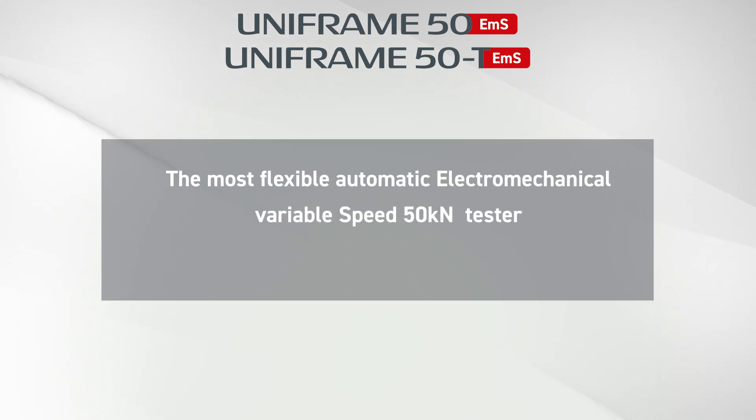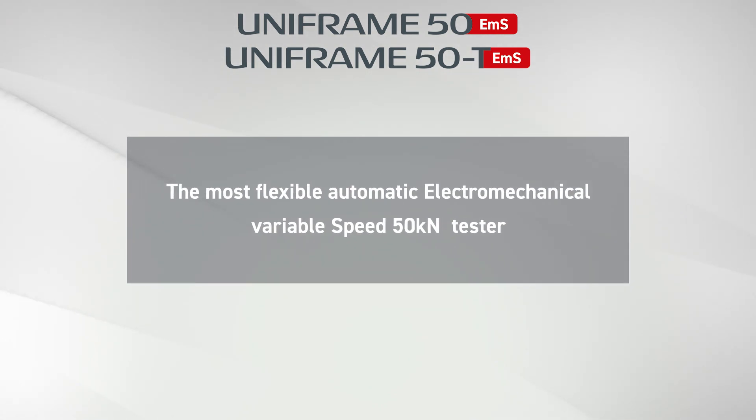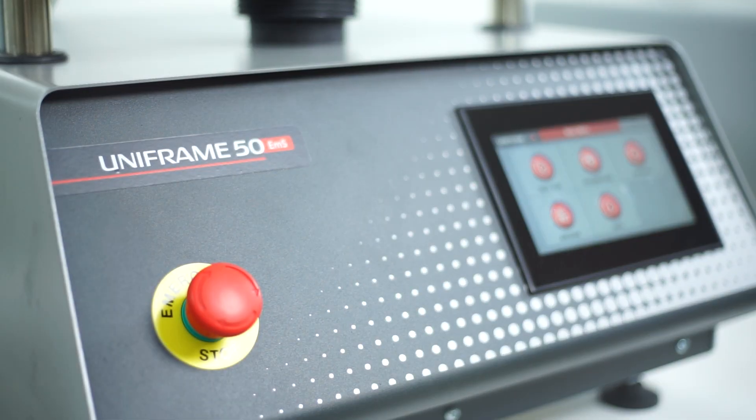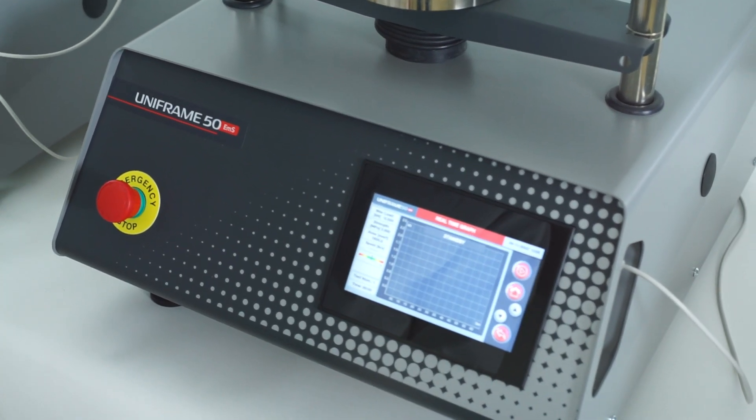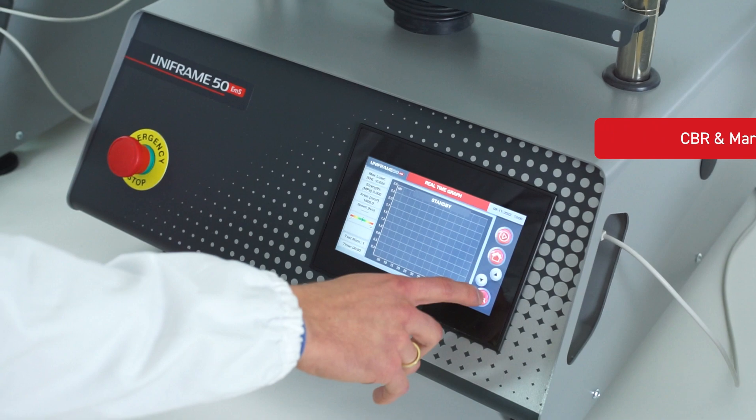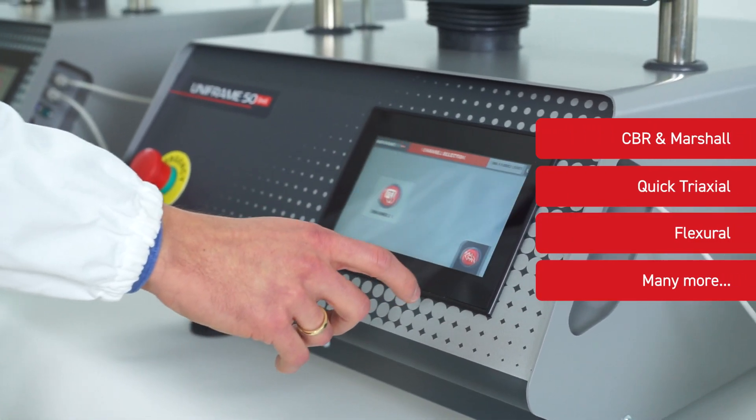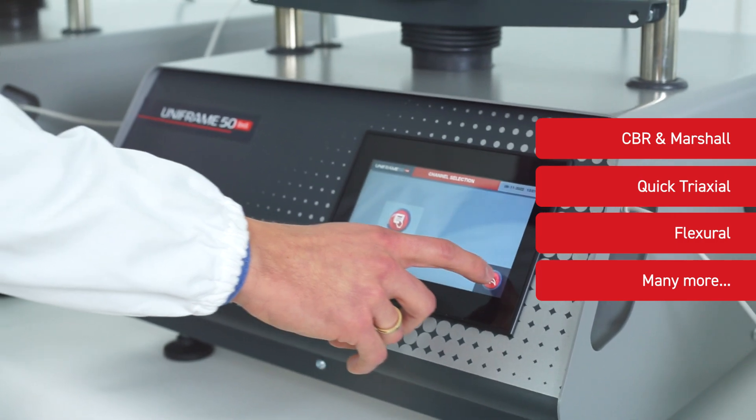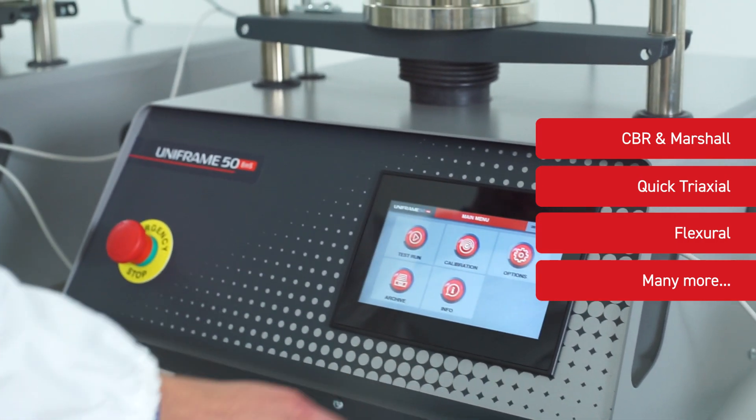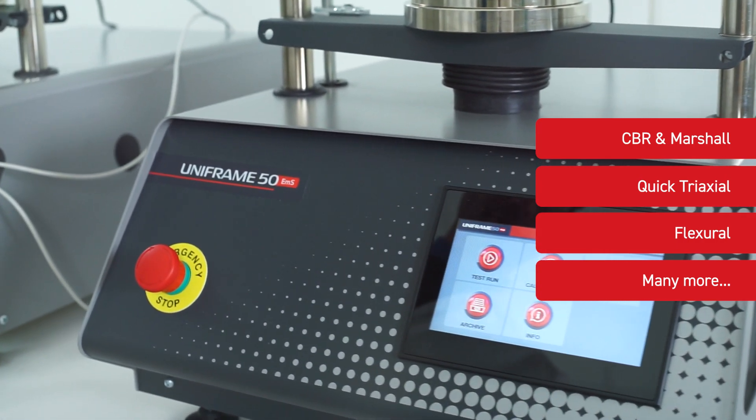The Uniframe 50 is the most flexible version in our range. Not only can it perform displacement control tests with the same features as the Multi-Loader, but it can also perform load control testing. Its large frame makes it suitable for many general-purpose testing such as CBR, Marshall, quick triaxial, flexural tests on beams and tiles, unconfined compression and punching tests.